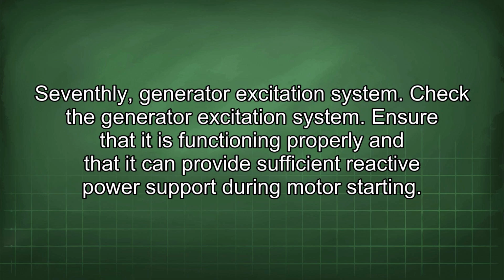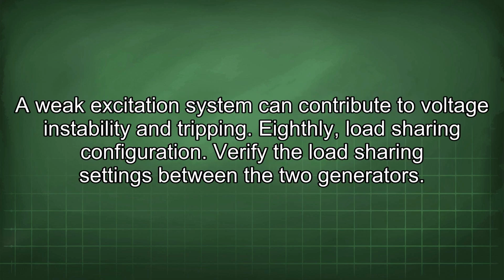Seventhly, generator excitation system. Check the generator excitation system. Ensure that it is functioning properly and that it can provide sufficient reactive power support during motor starting. A weak excitation system can contribute to voltage instability and tripping.